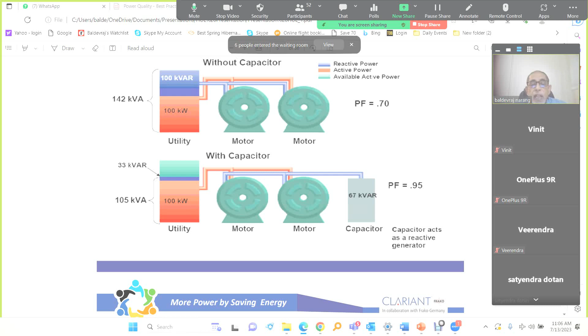And these days there is another component which is harmonics. I'll just add some more people who are coming. So harmonics also introduce a distortion power factor, and the harmonics have their own reactive power consumption as well. So what we ultimately get is the displacement power factor, which is the formula kilowatt by kVA. We have to multiply by this. Yes, sir. So we multiply this displacement power factor with the distortion power factor, and then we get the true power factor.